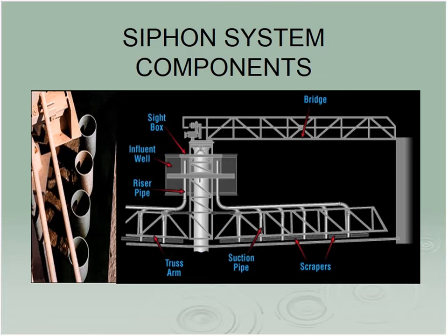Siphon systems, draft tubes, sludge recovery, whatever term you want to use, are very common with secondary clarifiers. Again, we're dealing with a relatively light material. So instead of plowing this down into a sump, a rake mechanism has blades that, instead of all being oriented in the same direction, now form a V. And at the apex of the V is a pipe that comes down. And all these pipes go up into a box that's isolated from the water in the clarifier.